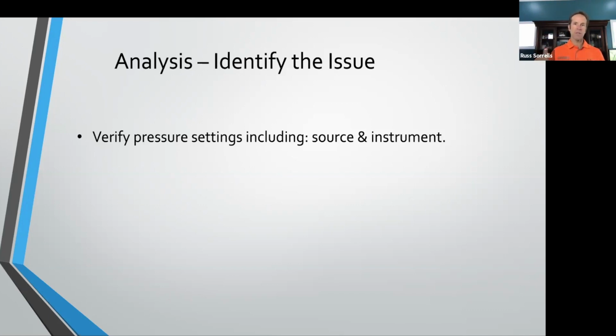Because if your instrument settings are incongruent with your target air pressure settings, then you will be frustrated because you press the start button and it's going to say overpressure. If you are overpressure, and then you will never reach minimum pressure if the target pressure settings are lower. But we also have in our instruments nowadays a pressure setting feature where you can just go in, select adjust pressure, and then just adjust the regulator accordingly.